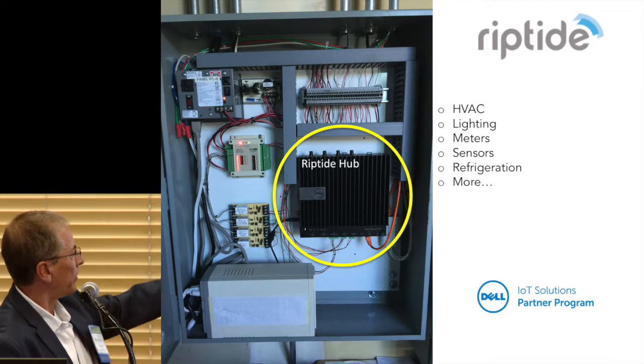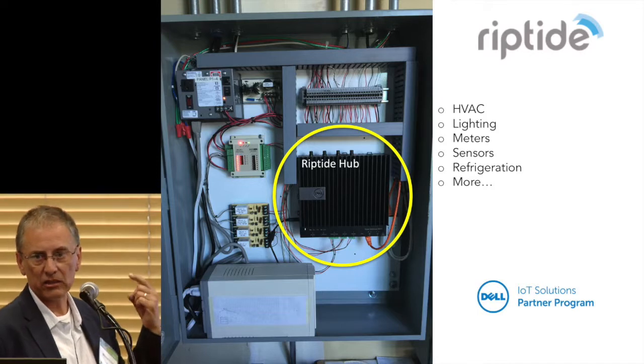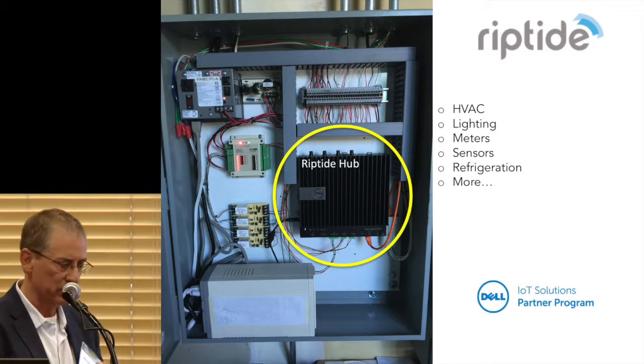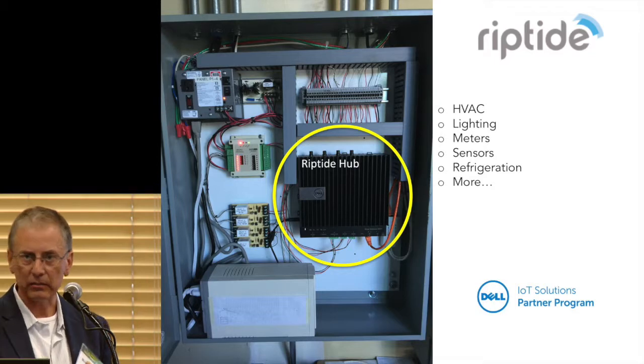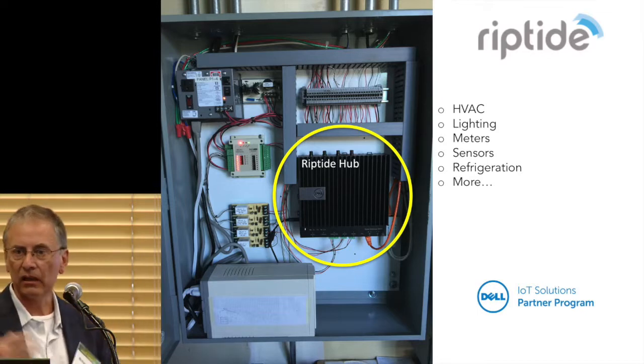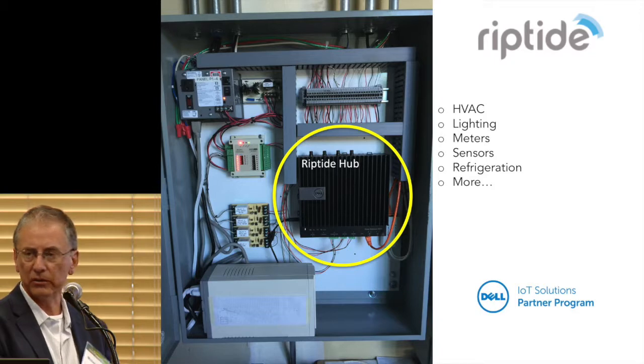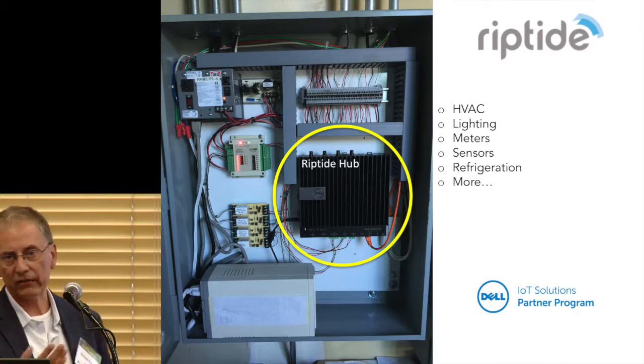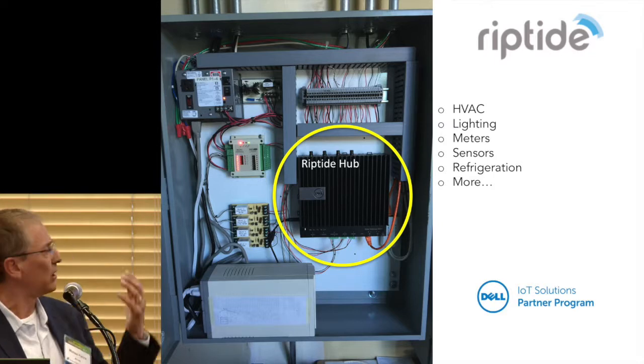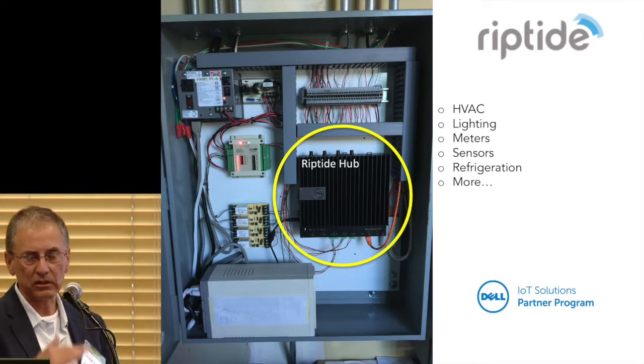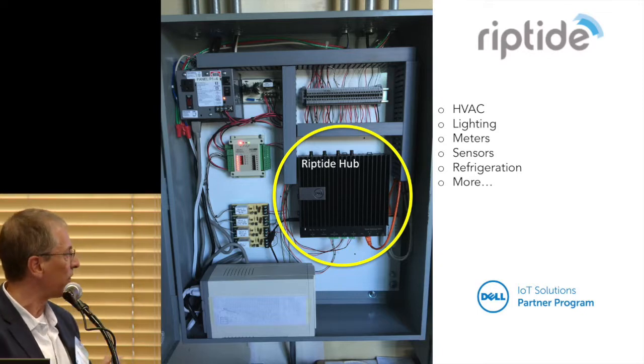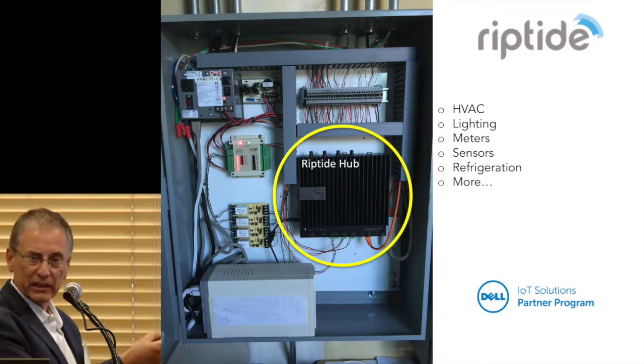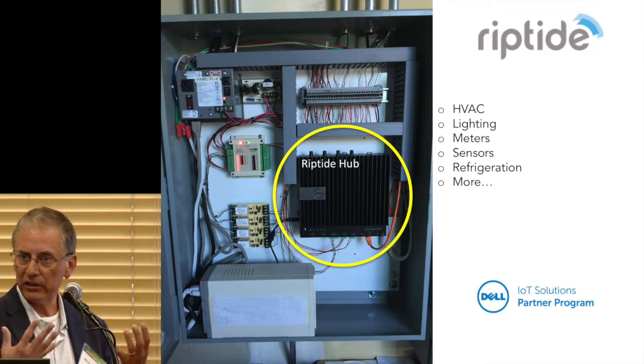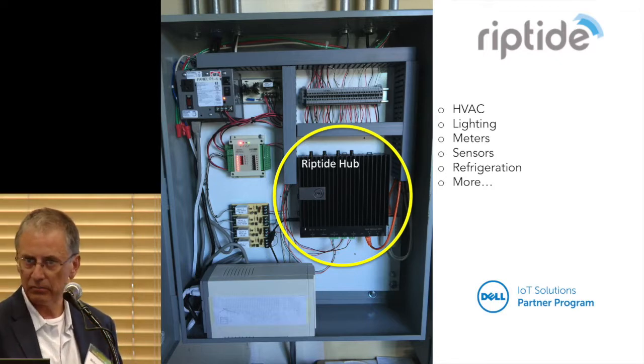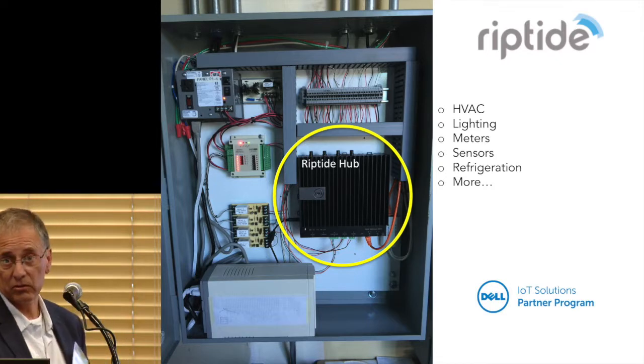So this goes in, has supervisory control over HVAC, can set the temperatures to whatever the occupants want, turn them off during unoccupied hours, do the same with lighting, measure the metered loads, send those meter readings up to the cloud. We can have logic in place where CO2 sensors, measuring CO2 levels independent from the HVAC, can affect the HVAC to open up fresh air access, bring in fresh air, and make a building more comfortable, and also increase efficiency.